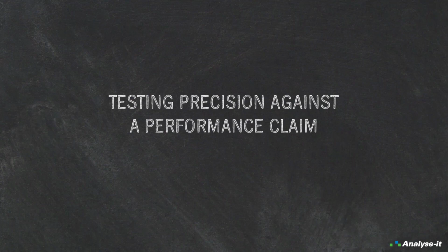Testing precision against a performance claim. You should perform this step when you already have a performance claim from a manufacturer's package insert and want to test whether your precision estimate is significantly greater than the claim. It is possible for the imprecision from a study to be greater than the manufacturer's claim, simply due to chance.